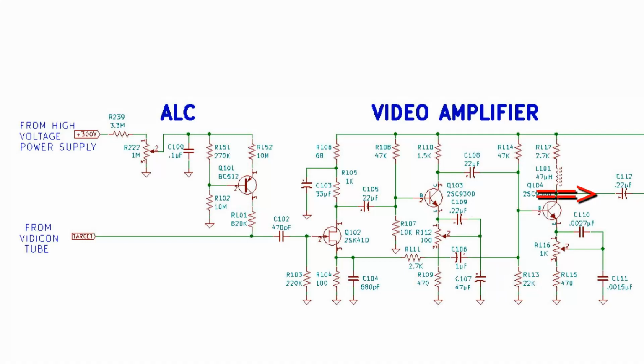The input impedance of the field effect transistor is approximately 200,000 ohms shunted by 10 picofarads due to negative feedback from the output through C106 and R111 to the source pin of Q102. Frequency compensation is adjusted by R112 and R116. These controls are adjusted for minimum trailing edges after a sharp transition from black to white or white to black.